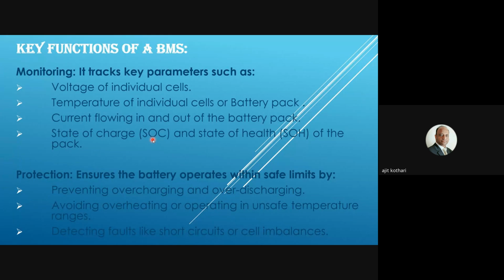Now the protection part. Protection prevents overcharging of the battery. For example, day to day mobile charging - most people keep charging the whole night. But the mobile will get charged in 1 or 2 hours now, because fast chargers are available with mobiles also. So if you forget to remove the charger, BMS is there to protect the battery - it will automatically switch off the power coming from the charger and not give it to the battery. Inside, MOSFETs are there that switch off the charging current given to the battery bank. That is how it protects your battery bank from overcharging.